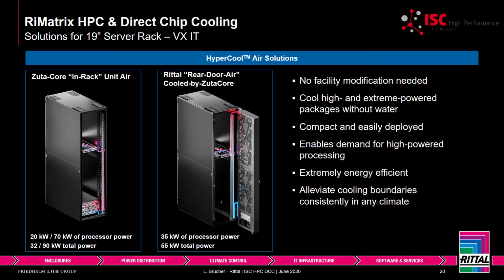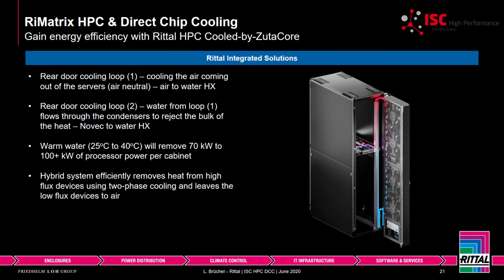On the side of it is the rear door cooling unit. This unit allows cooling 35 kilowatts of processing power and 55 kilowatts of total power per rack. Both of these units, you need to change nothing in your data center. No extra pipe, no extra installations. You just come in with the in-rack unit, or you change the door with the airflow door, and it's already installed. Here is a feature which is coming in the future, a water-cooled rear door. It will allow increasing the cooling capacity all the way to over 100 kilowatts per rack. But this is coming up.